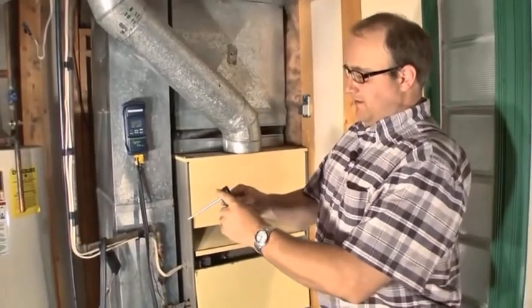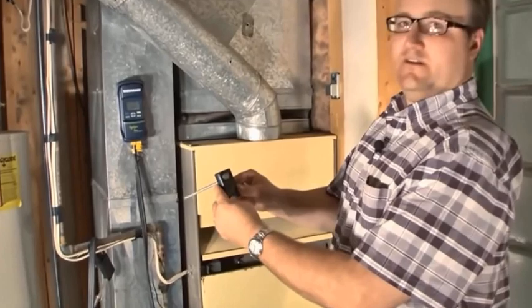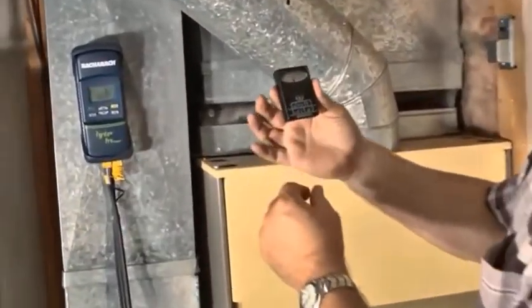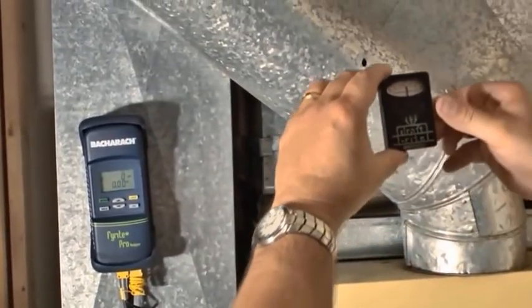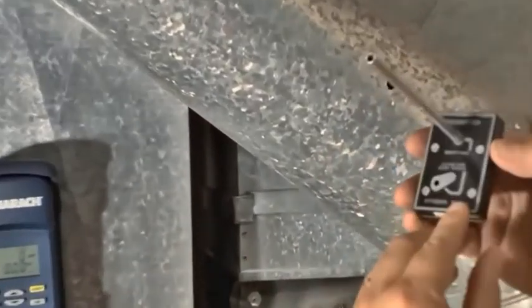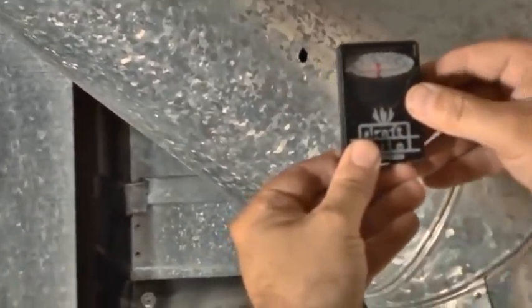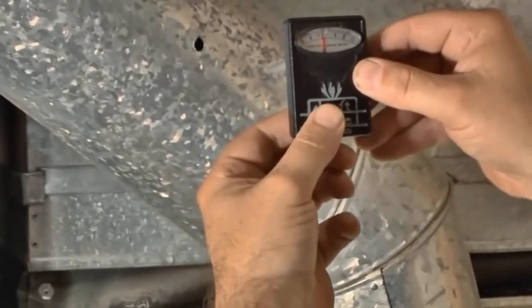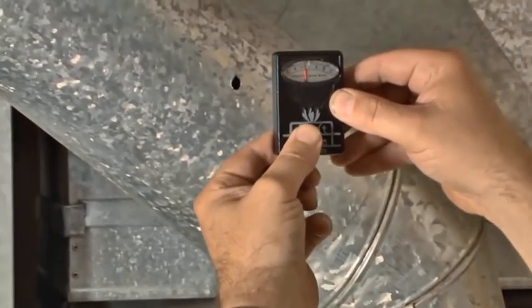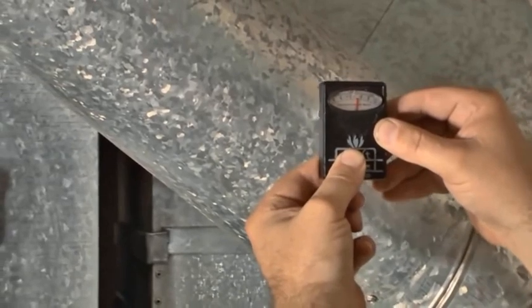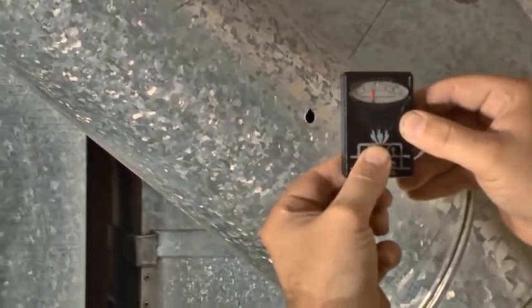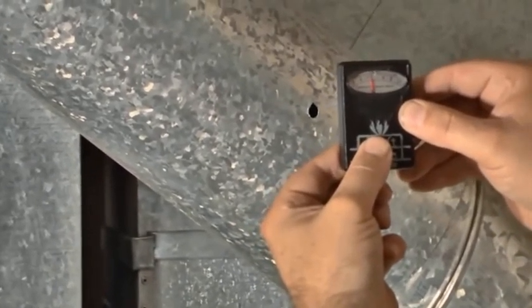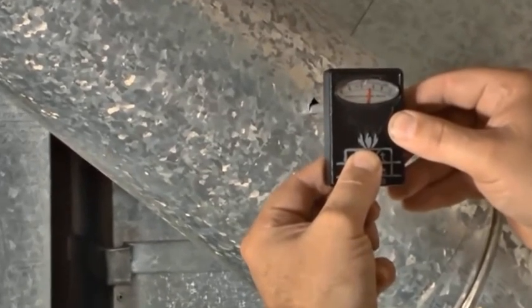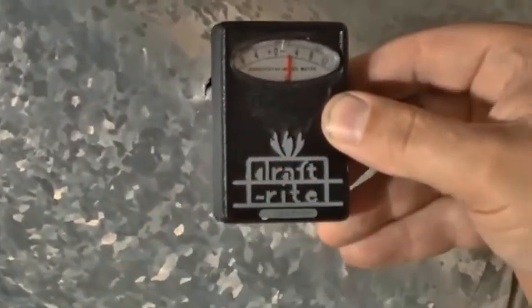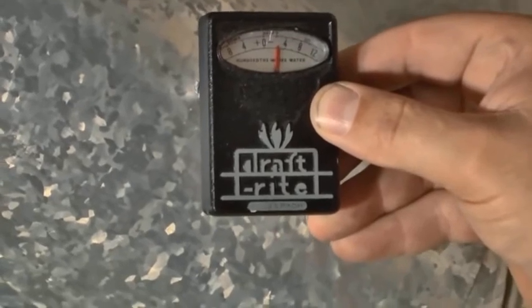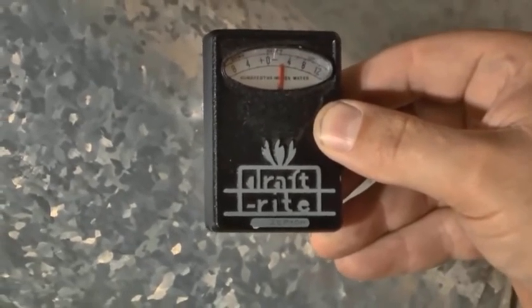Okay, this is another method of measuring the draft in the flue. This is a draft gauge. What you do is there's a hole on the back. You level this thing out, stick your finger over the hole, and then you stick it into the hole for reading draft. Okay, I need to make sure I get it leveled out.